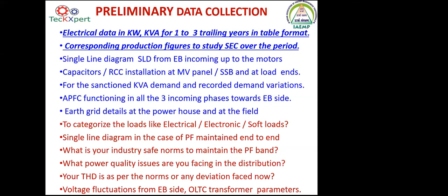That is why I said, what is the power factor band that is to be safely kept in the industry? That industry was maintaining a power factor of around 0.95 to 0.96. So each and every industry, if it is kW billing and not kVAh billing, can have a safe power factor loading band with which the harmonics, or the excess power capacitors, or excess amplified harmonics due to capacitors, can all be avoided.